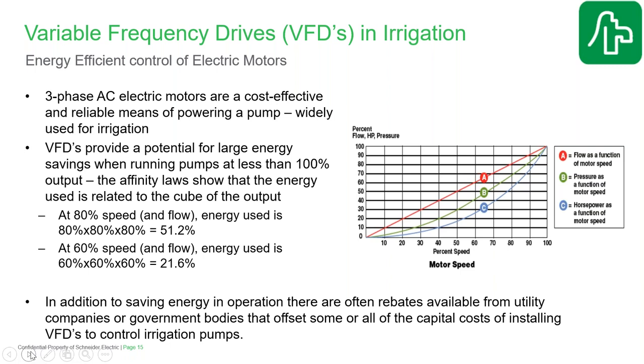As Jack showed you earlier, your energy usage is going to be up to 40% of your total cost of owning and operating that pumping system. So if we can significantly reduce that energy use, we can significantly reduce that overall cost. And in addition, due to the energy saving initiatives being driven by both government bodies and utilities, there's very often rebates available to offset some of the capital costs for installing VFDs to control pumps in an energy efficient manner. So not only can you reduce your 40% of your ownership costs for the energy use, but you can reduce some of that 10% of the capital cost of purchasing and installing the pump as well.